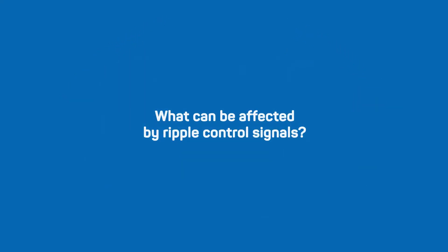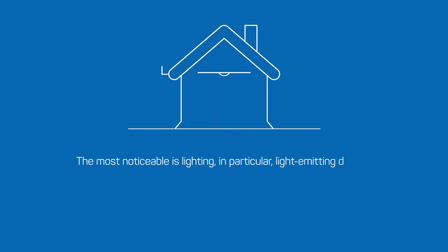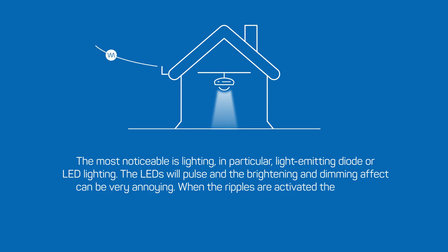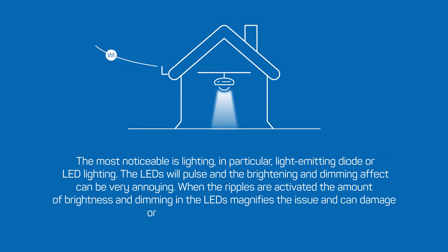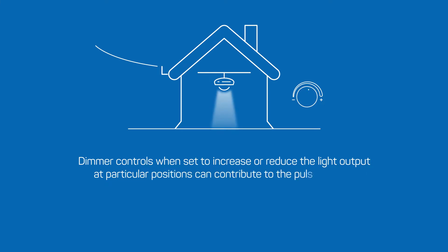The most noticeable devices affected by ripple control signals are lighting, in particular light emitting diode or LED lighting. The LEDs will pulse and the brightening and dimming effect can be very annoying. When the ripples are activated, the amount of brightness and dimming in the LEDs magnifies the issue and can damage or reduce the LED life expectancy. Dimmer controls, when set to increase or reduce the light output at particular positions, can contribute to the pulsing effect of the LEDs they are controlling.